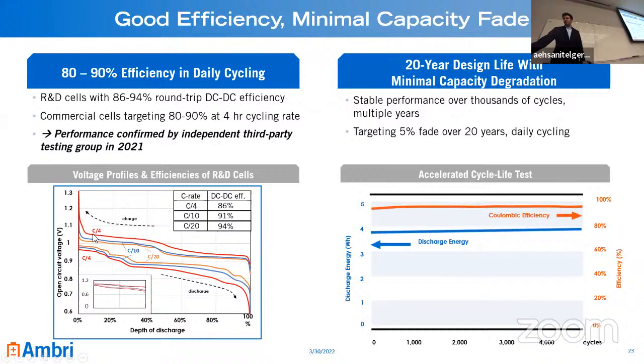You can see here the C/4 batteries, the red lines, are furthest apart—this is the most overpotential, so the charge and discharge voltage profiles are separated the most. The 10-hour and 20-hour rates are closest, because as we discharge more slowly, there's less voltage drop in the battery, so the round trip efficiency goes up. It's easy to go slower in our battery, and in most batteries.